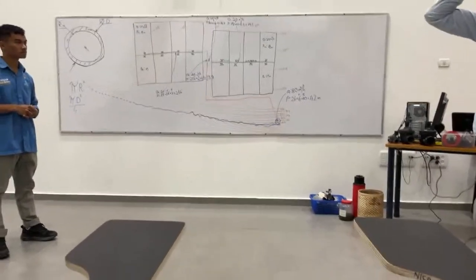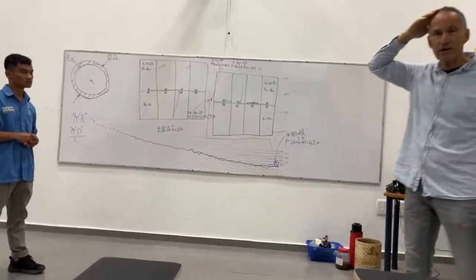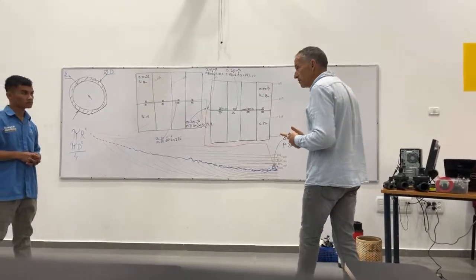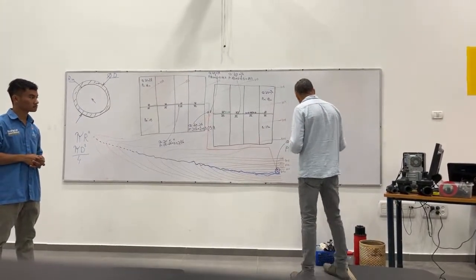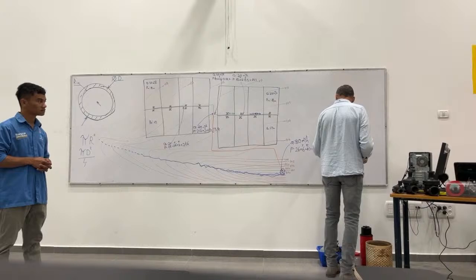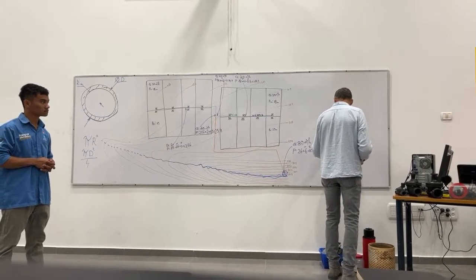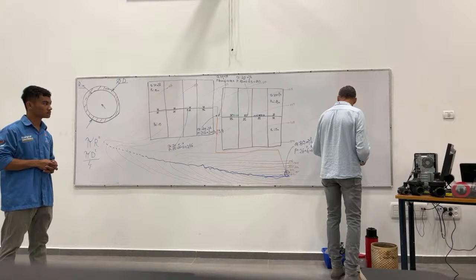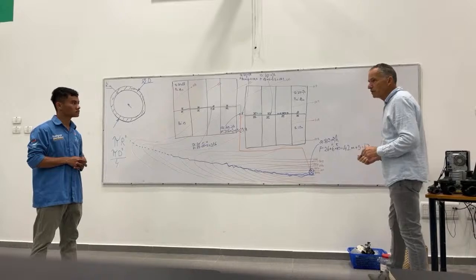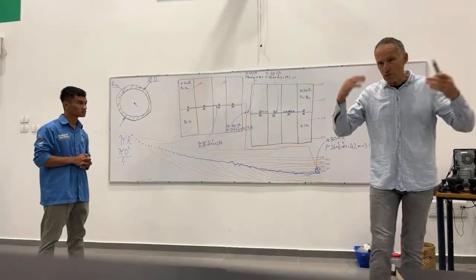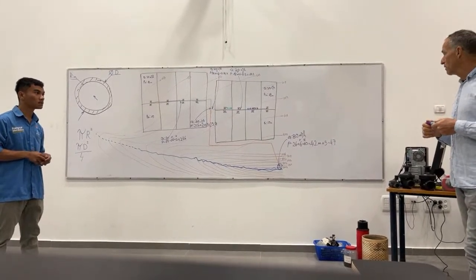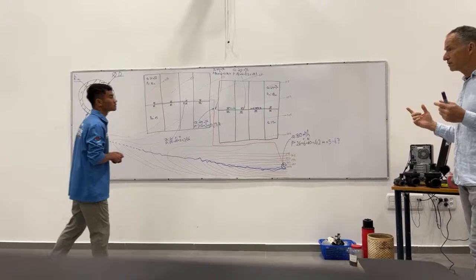You remember that we said that automatic filter we always do backwash after half a bar, 5 meter or 50 kPa. Then we need to consider also the filter. We're also going to add here for the filter another 5, and we're coming to 47, and that is going to be our duty point for the pump. 47 meter, and again you can round up to 50, and that is what we usually do. 5 meter for the filter.